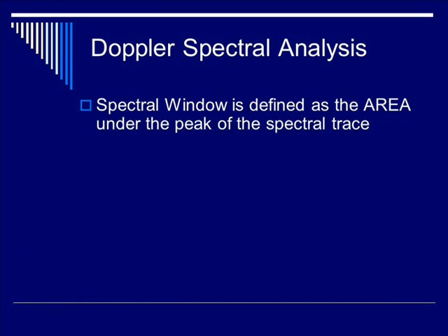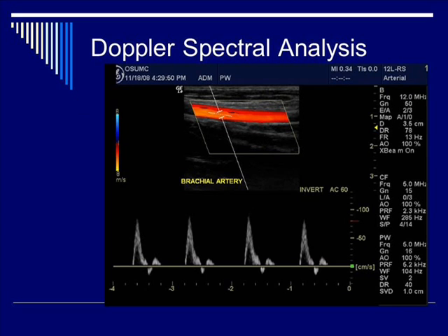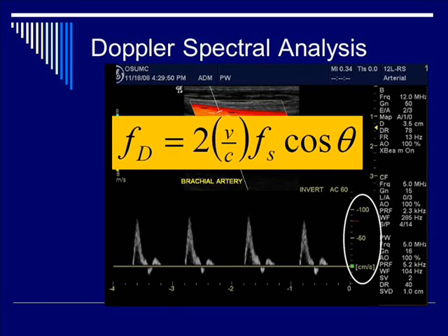The spectral window has a specific definition: it is the area under the peak of the spectral trace — the empty area seen in the display. On the y-axis you have velocity, which comes directly from the Doppler equation: f(d) equals two times velocity divided by the speed of sound, times the source frequency, times the Doppler angle term. This velocity v corresponds to the v plotted in the chart.